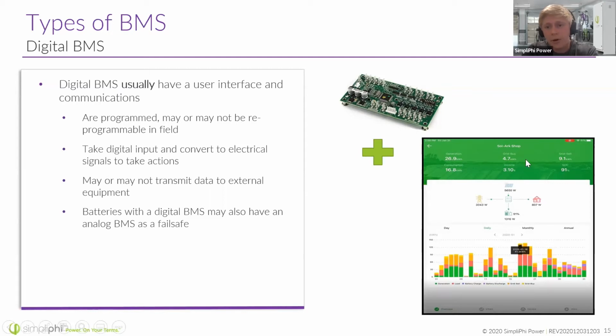For example, you can program in a low voltage cutoff of maybe 20 volts into your 24 volt BMS, and it will then take action instead of only relying on that value across a component. A battery with a digital BMS might also have an analog BMS as a failsafe or backup — they can definitely work in tandem.